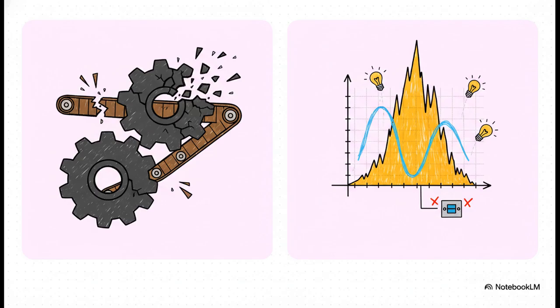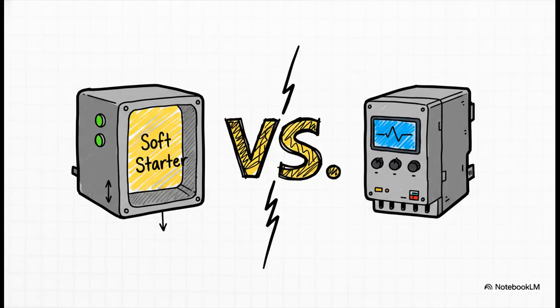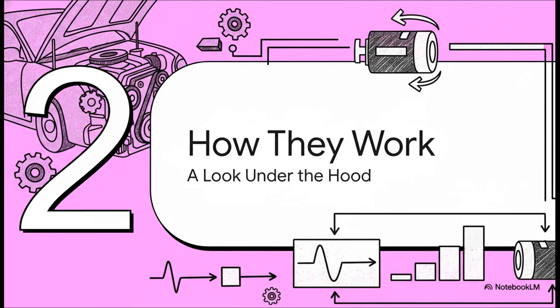And then on the other side, you've got the electrical surge. We're talking about an inrush current that can be 6, 7, even 8 times what the motor normally uses. That can cause lights to flicker, trip circuit breakers, and just put a massive strain on the whole power system. And that brings us right back to our two contenders for taming this beast. You've got the straightforward, no-nonsense soft starter, and then you have the more complex, more capable variable frequency drive, or VFD. So how do they actually pull this off?